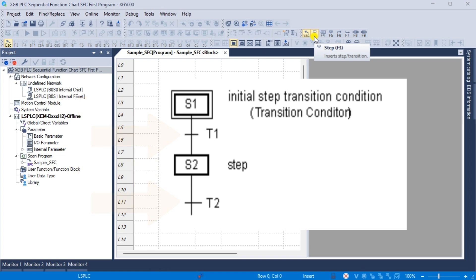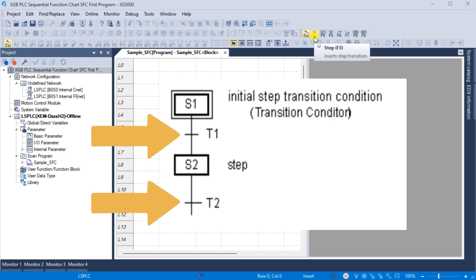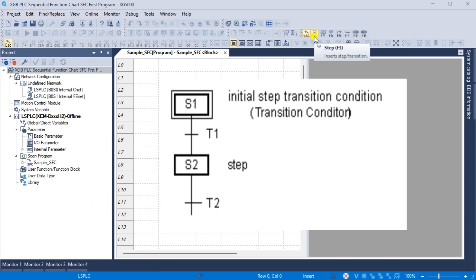Transition: a transition indicates the conditions required for execution between steps. Each transition condition must be expressed using PLC language, either in structured text or ladder diagram. The result of the transition condition must always be a boolean type and the variable name should be 'trans' for transition. If the transition condition evaluates to true, the current step is deactivated and the next step is activated. Transitions are mandatory between each step.